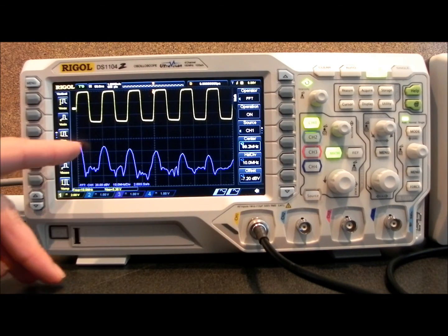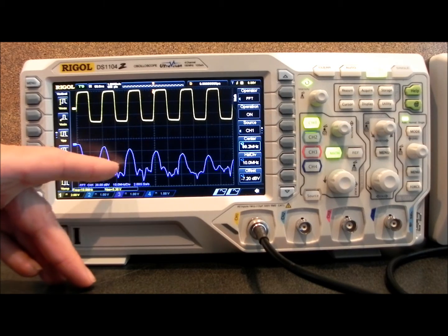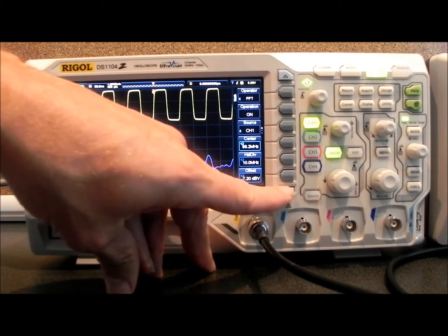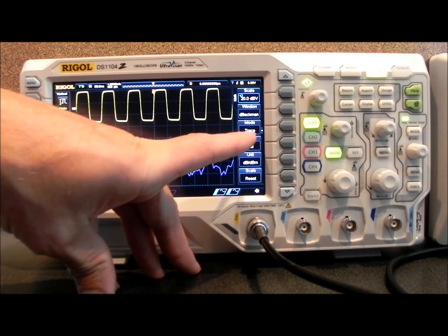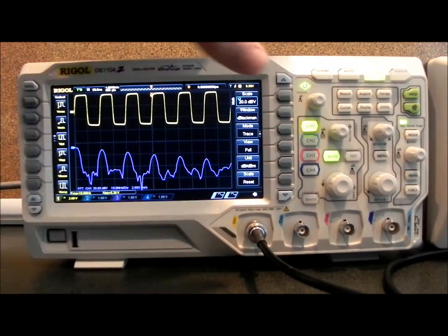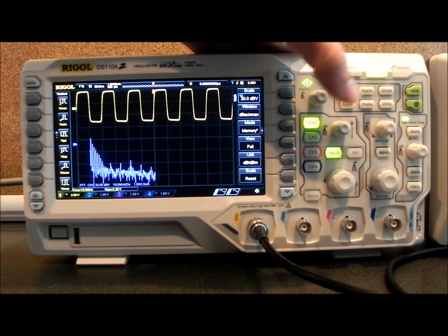What I'd like to show you, though, you can see the peaks, but then in between the peaks we don't really have a lot of detail. We'll go down to the second page in the menu, and you'll see that the mode is set at Trace. Now, we can expand that to Memory.